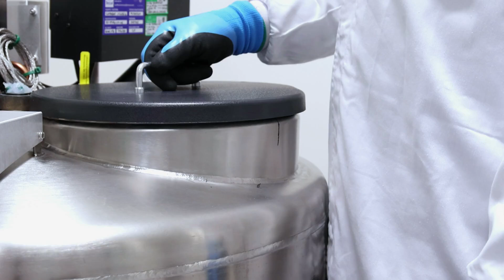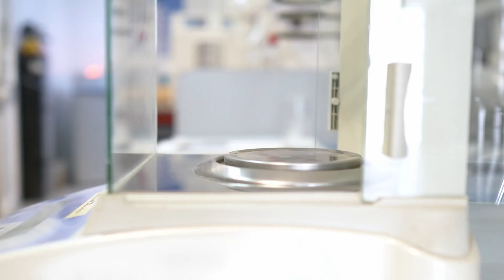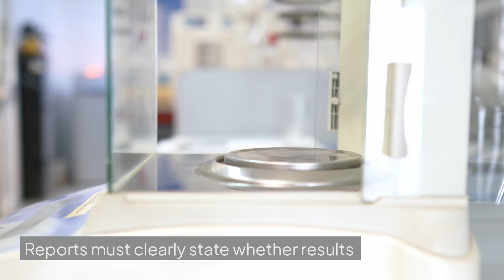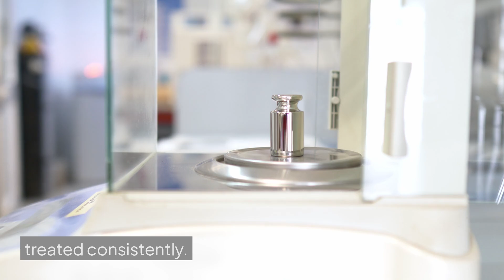Cement and related powders introduce moisture, fines loss, and reporting basis risks. A stable weighed mass may not represent the intended dry material if moisture remains uncontrolled. Laboratories may need defined drying conditions, sealed storage, consistent powder transfer, and checks for lost fines. Reports must clearly state whether results are on an as-received or dried basis, with calibration and quality control samples treated consistently.